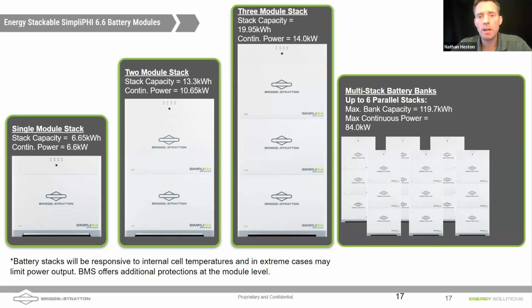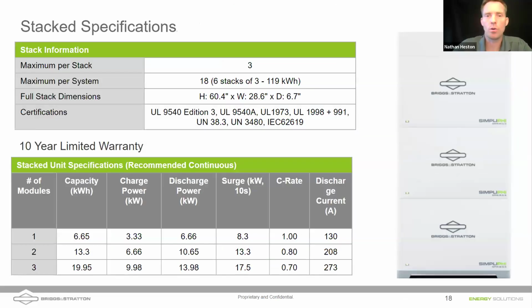If you want to do a 15K, the minimum we'd recommend is a 3-stack minimum, and that'll deliver full power to a Sol-Ark 15K as well. We are limited in terms of the total number of stacks we can run in parallel. Each stack of 3 batteries is 20 kilowatt hours, and we can do up to 6 parallel stacks. Of course, you could have 2 stacks of 2 batteries as well, depending on your needs — they don't all have to be stacks of 3. But we don't encourage, for balancing reasons, pairing a 1 stack with a 3 stack. You could do a 2 stack and a 3 stack, but I wouldn't encourage too much imbalance, because that's harder on individual batteries — we need to do a bit more with the cabling to balance things.